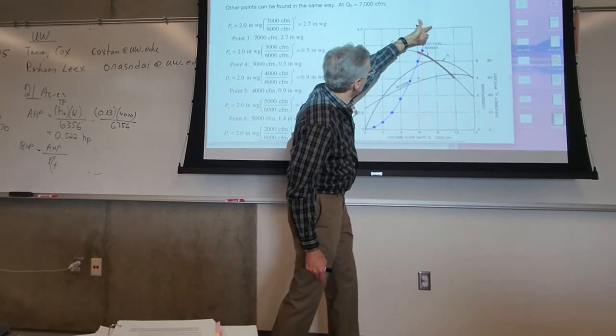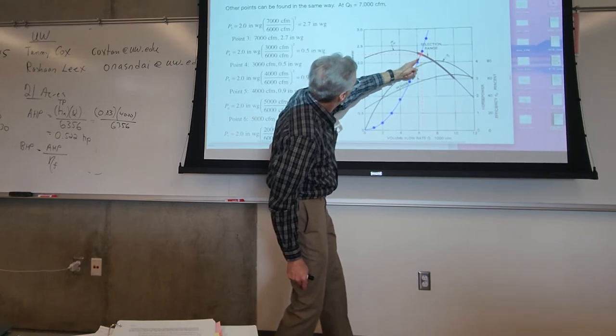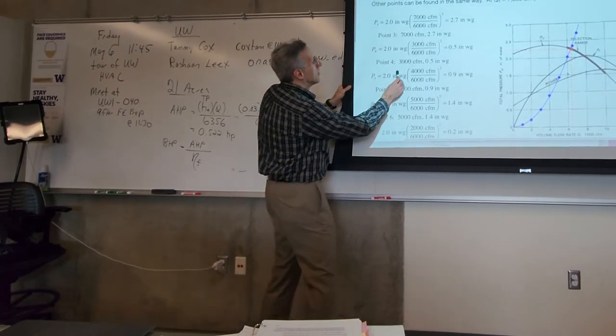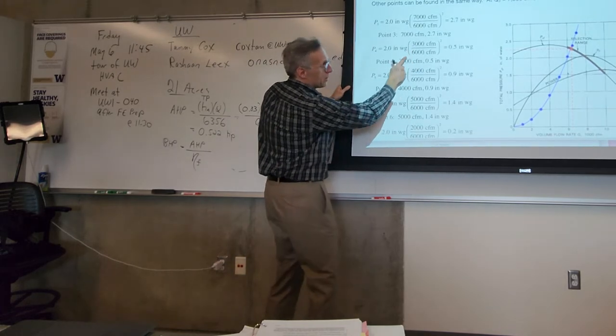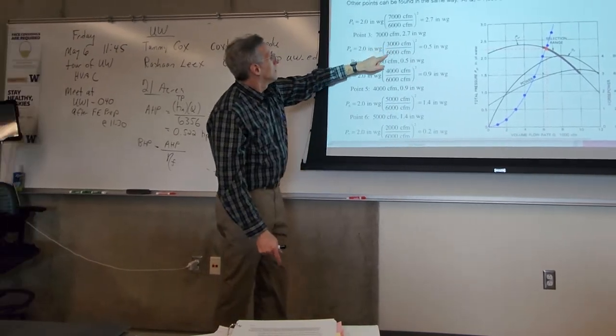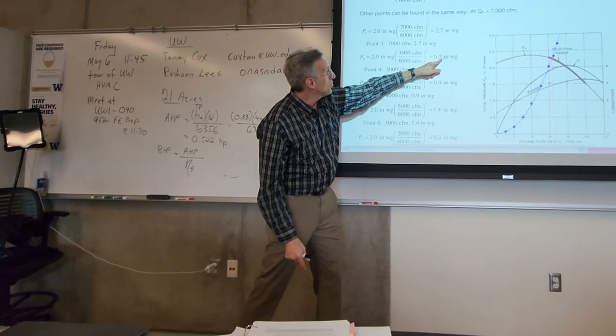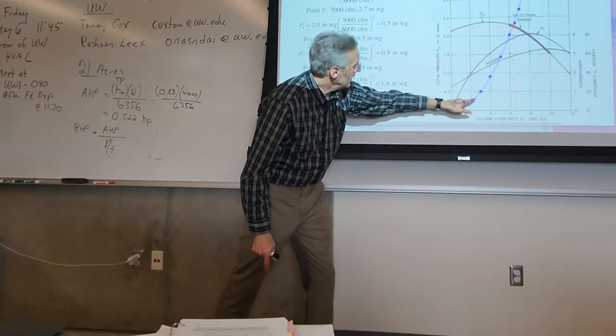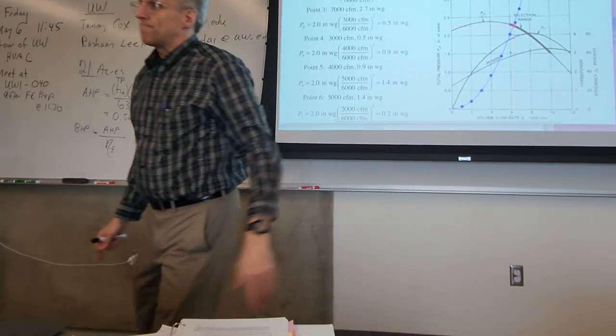Now we've done the high side. If we go any further, we're going to go off the chart or be near the edge of the chart. Let's now go lower. What if we dial down the CFM? I went all the way down to 3,000 CFM, so I went down to that point there. So here's my original pressure, my original CFM, and now my new pressure is 0.5. So at 3,000 CFM, I have 0.5 inches of water. And I just keep doing that until I have enough points that I can make a curve like that.